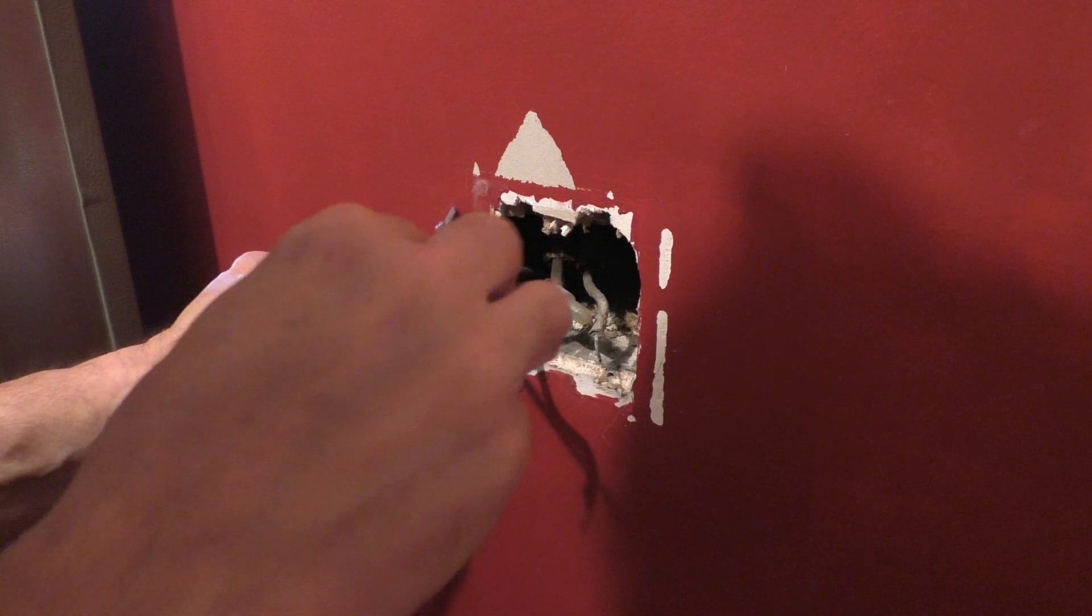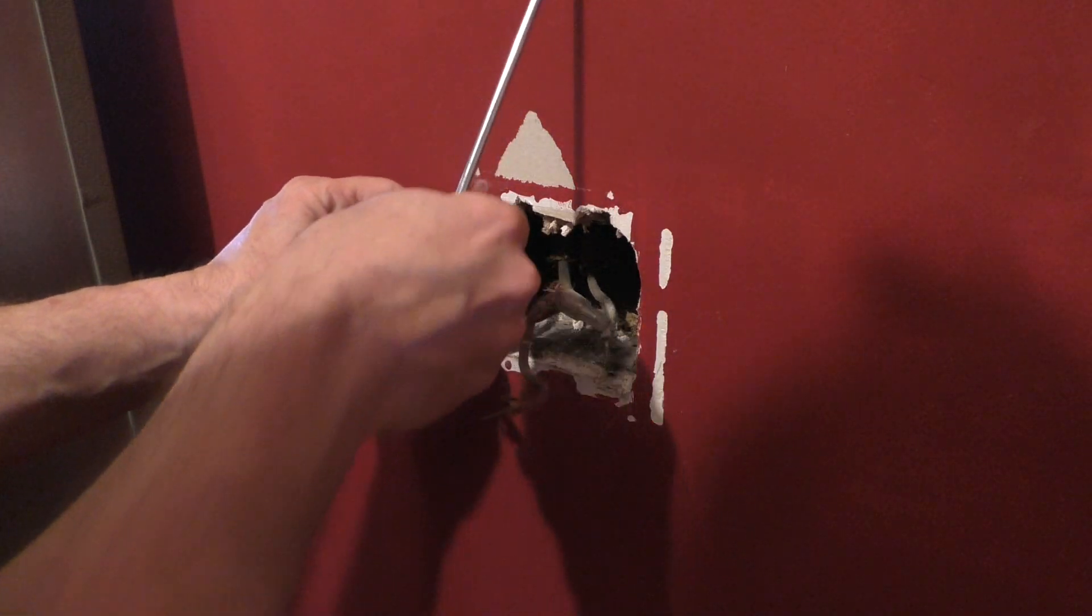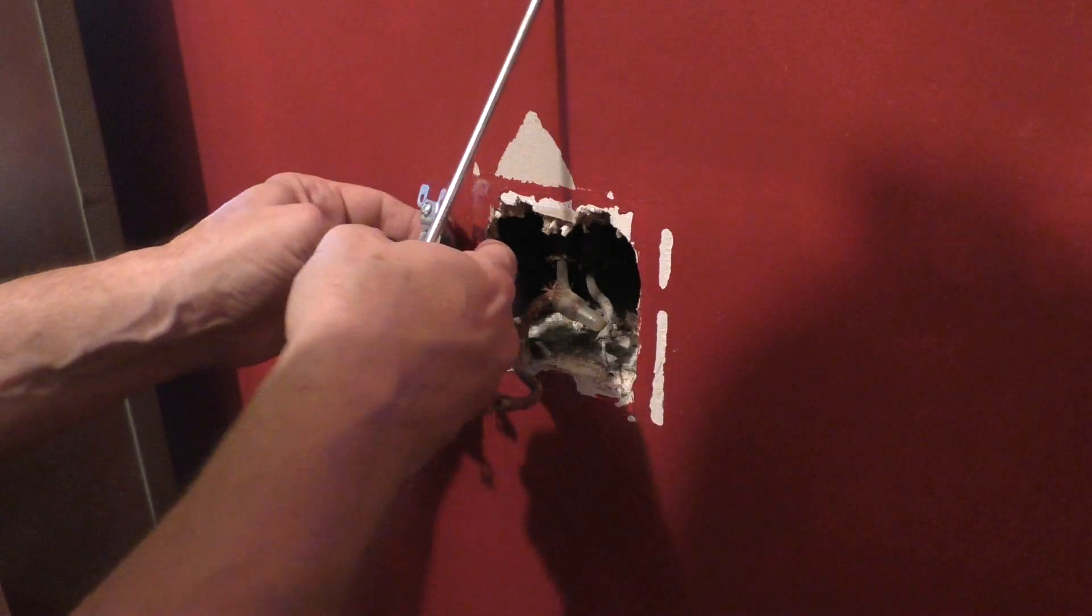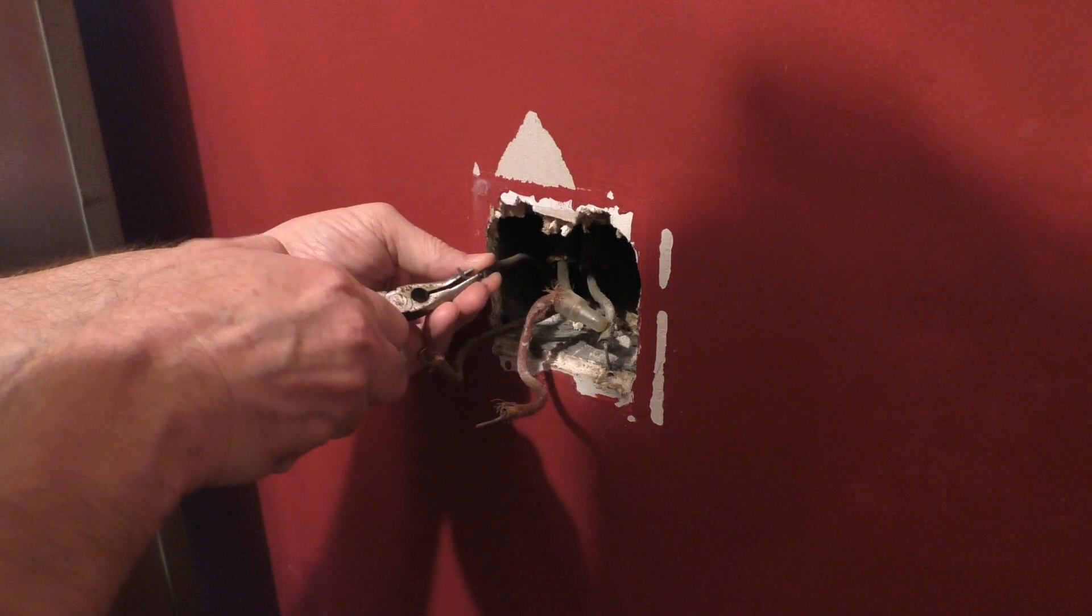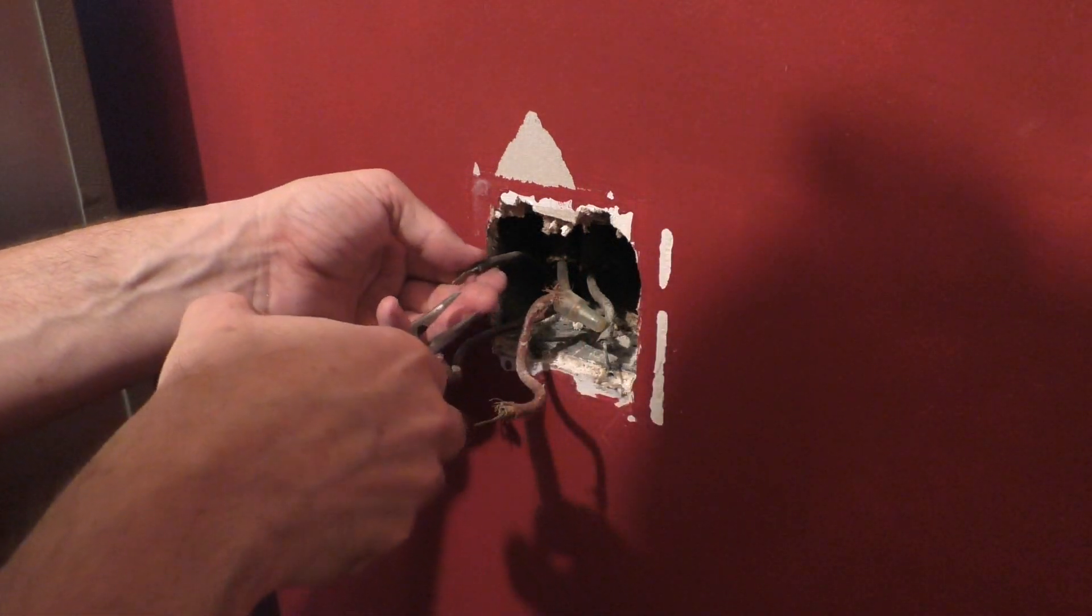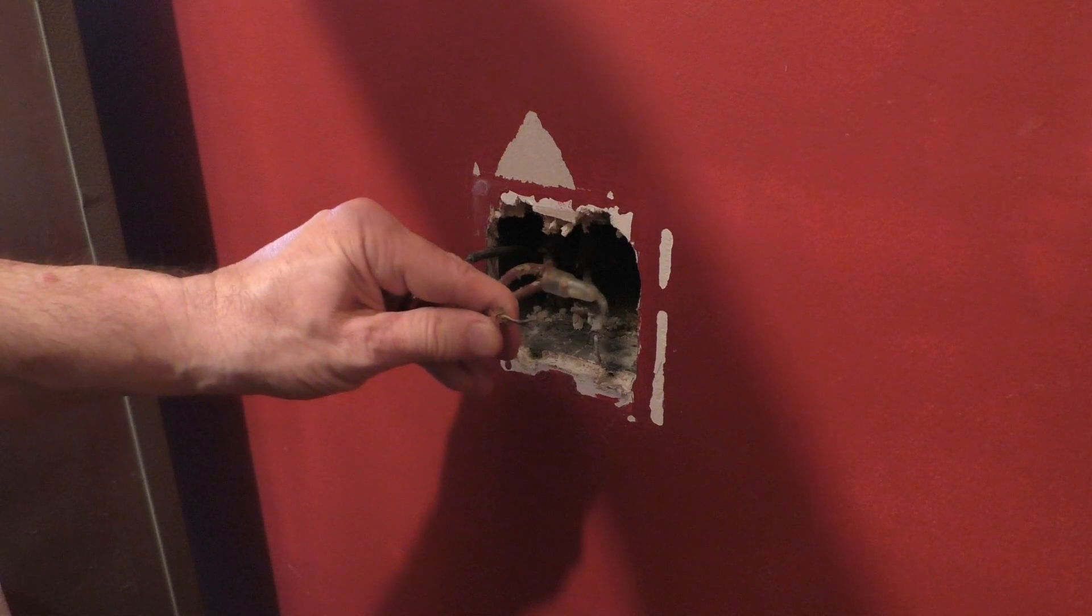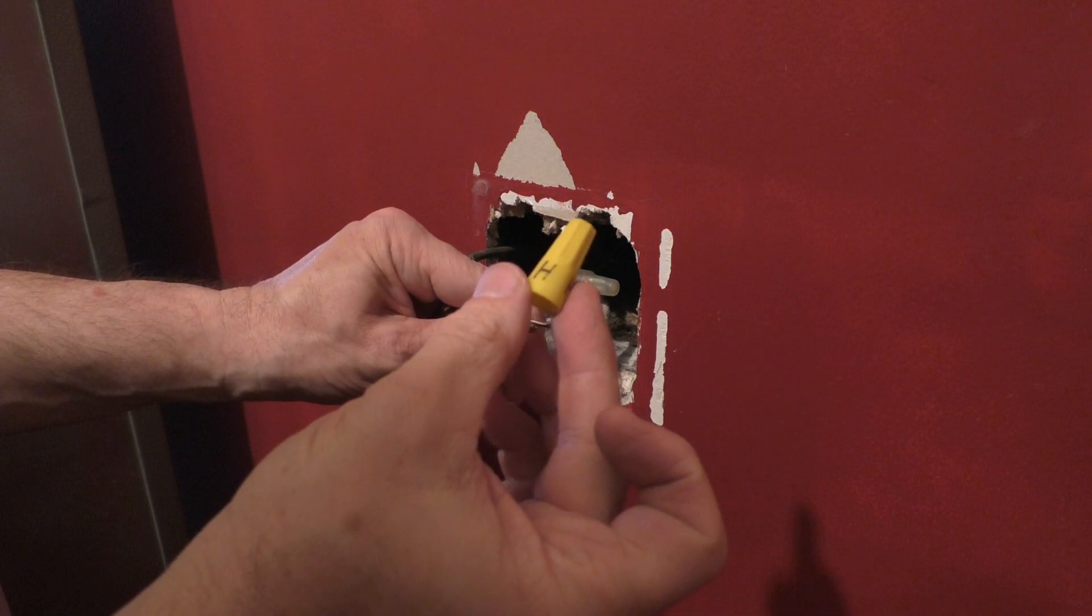The wires for the left light switch were connected to the screws, so they just came out by loosening the screws. I then straightened all the wires and inserted wire caps on each wire, even the dead ones. I did mark the cap for the hot wires with an H for future reference.